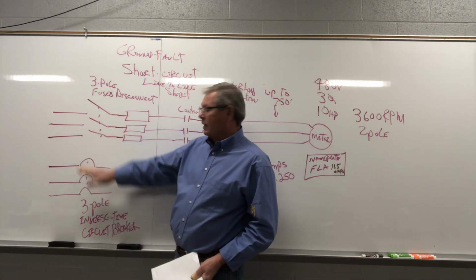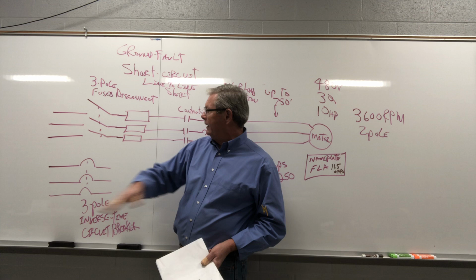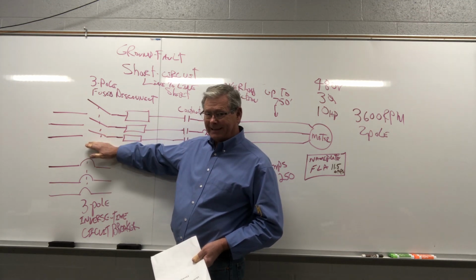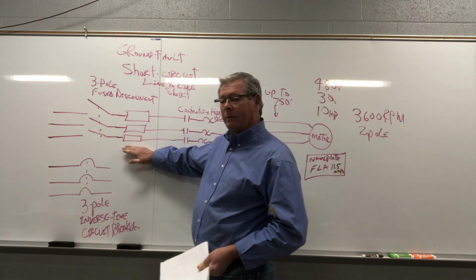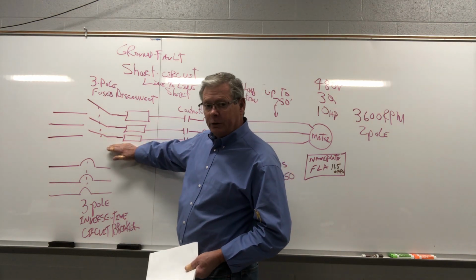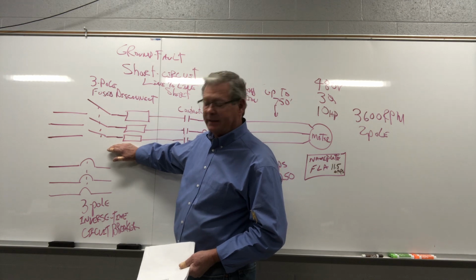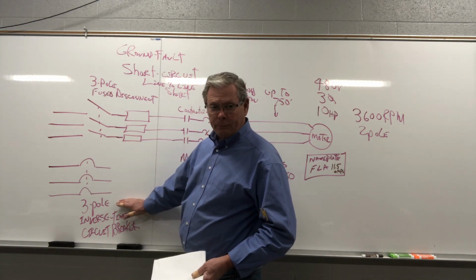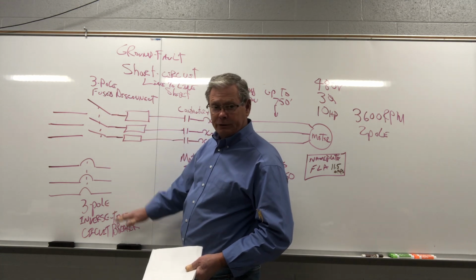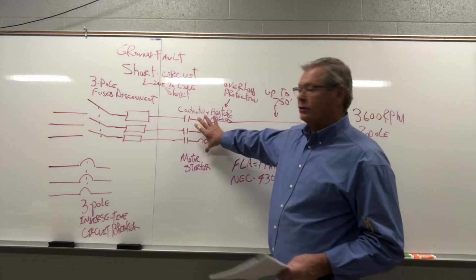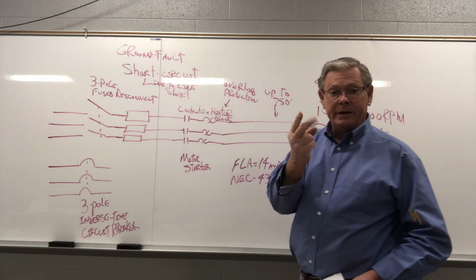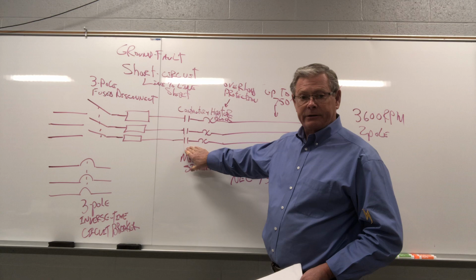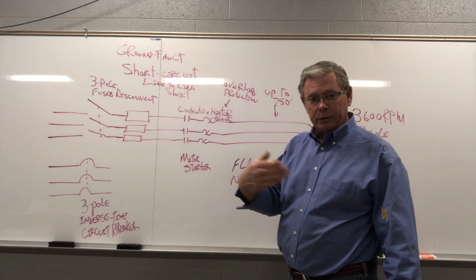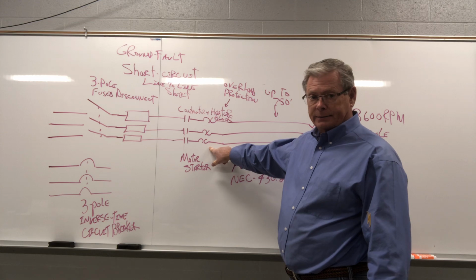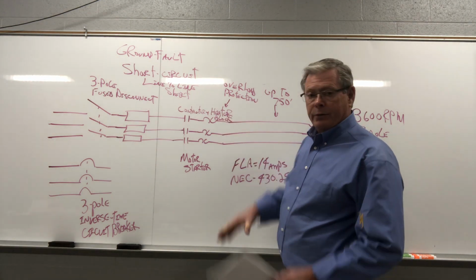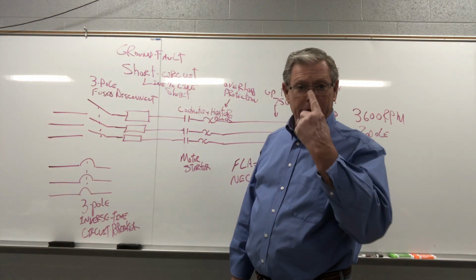So we can accomplish being able to disconnect that motor in one or two ways. We can either have a 3-pole disconnect, and then they normally have fuses with them, so it'd be a 3-pole fused disconnect, F-U-S-E-D, fused disconnect. Or it can be a 3-pole circuit breaker for 3-phase. Either one will accomplish both of them, okay? Then we have a starter. A starter is made up of two different devices. A contactor, which opens and closes and applies your power to the motor, starts and stops it, and then a heater block, okay?